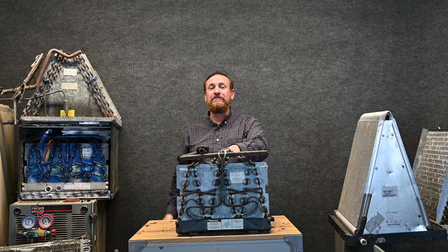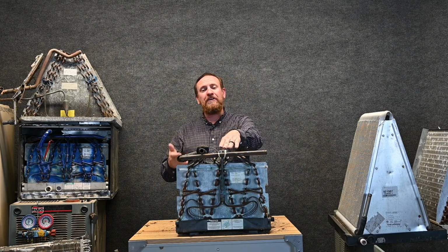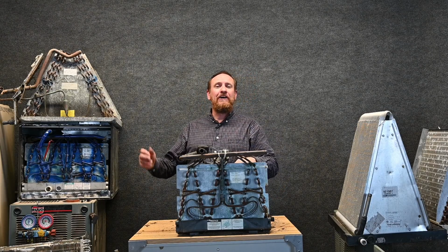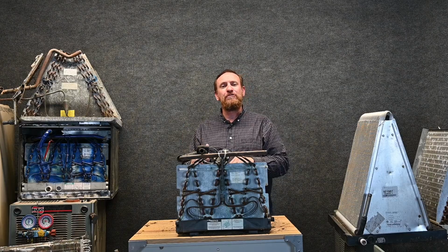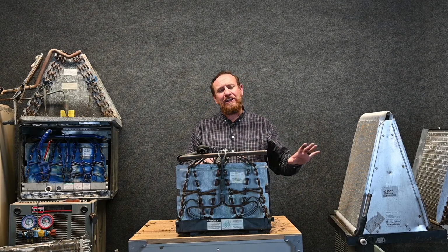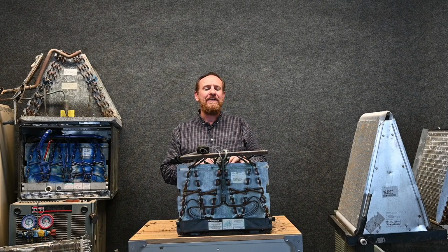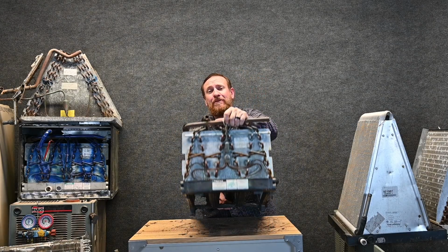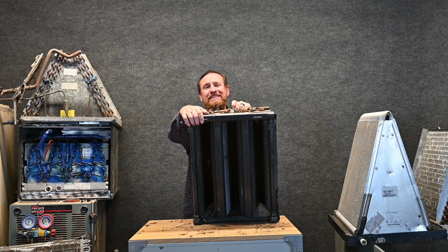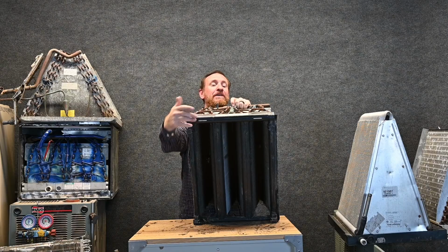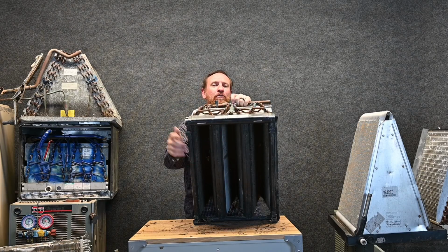So now the next guy knows, hey, look at subcooling, and then we'll also check superheat to see if it's working right. If it is a true fixed orifice, I'll know I'm going to need return air wet bulb and outdoor dry bulb to calculate target superheat and actual superheat. And then I'll look at subcooling as a secondary. So we want to look at that whole entire system, but again, if the evaporator coil is dirty, superheat and subcooling really isn't going to matter because we're not going to be able to transfer heat like we need to. So checking the airflow, checking the condition of that coil is going to be very important.